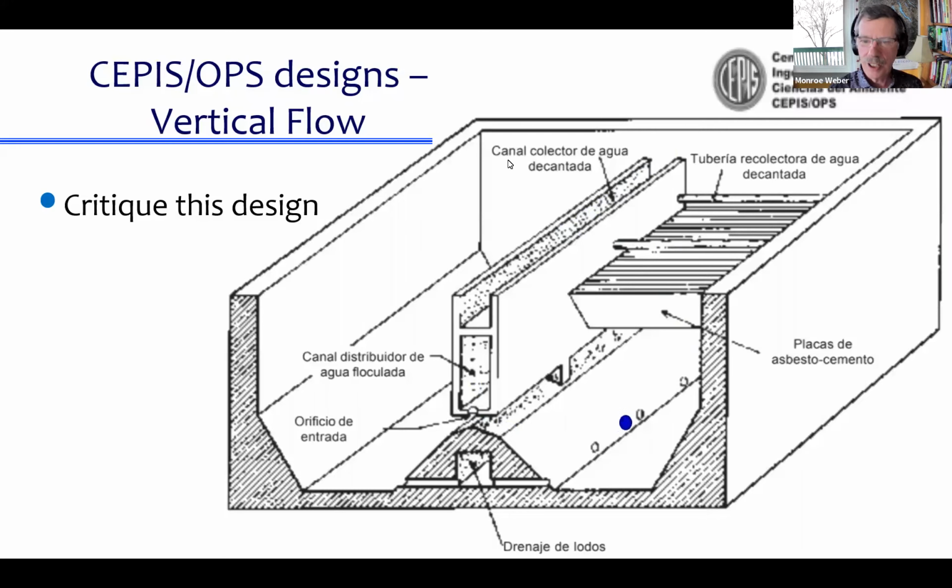Oh, there's a great question. Are those plate settlers made of asbestos cement? And that is exactly what they say. They are made of asbestos cement. And I'm betting you're thinking that's not a good idea. And you are right, it's not a good idea.